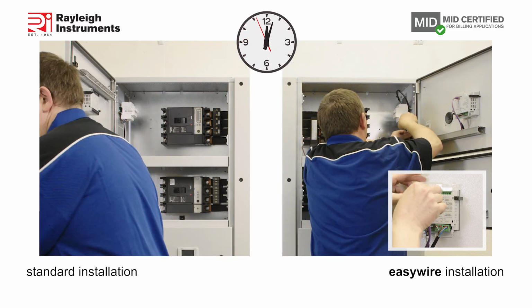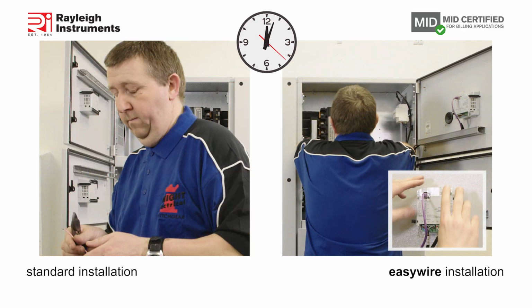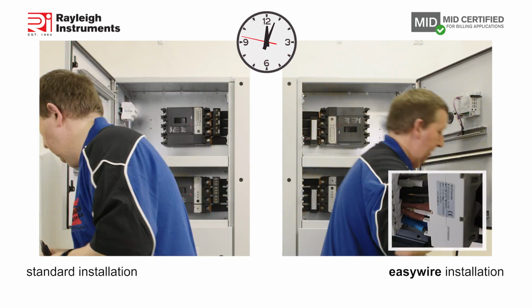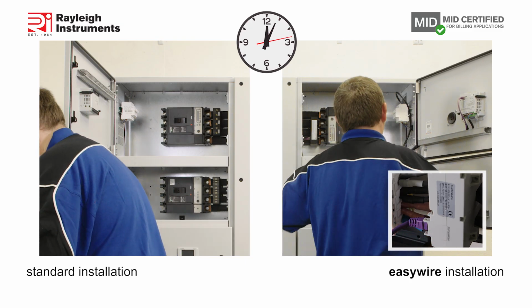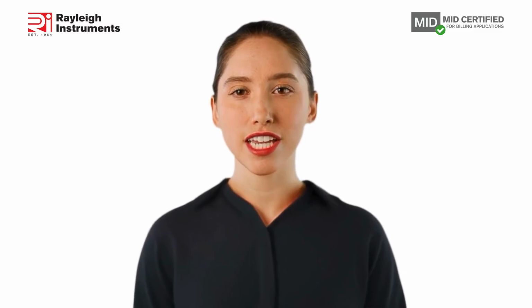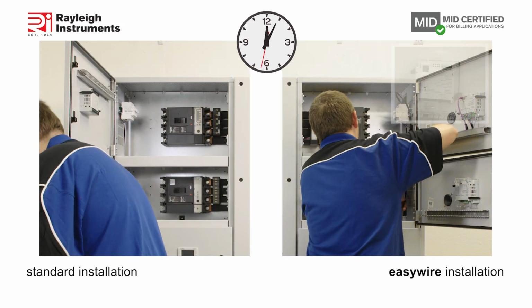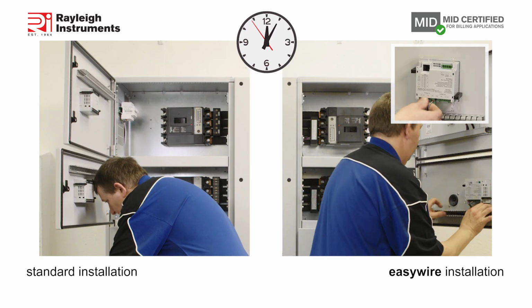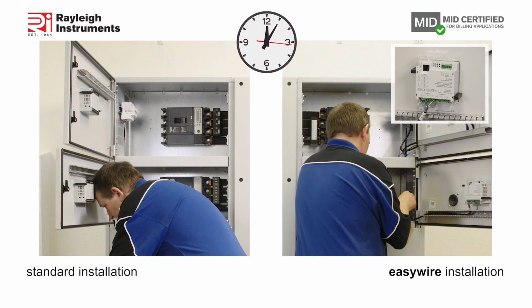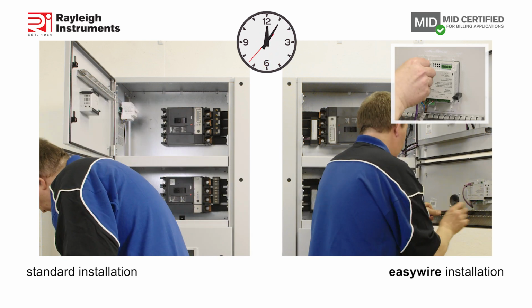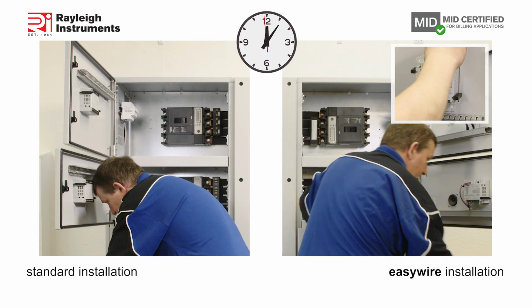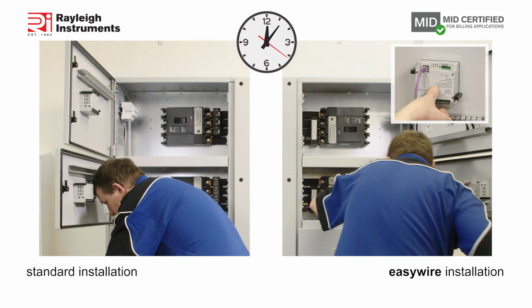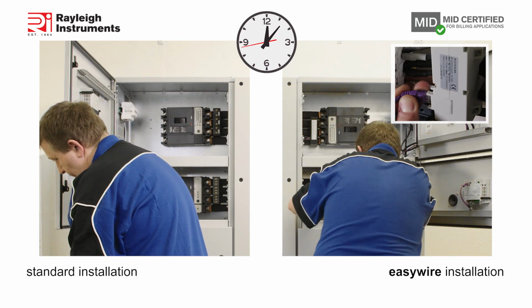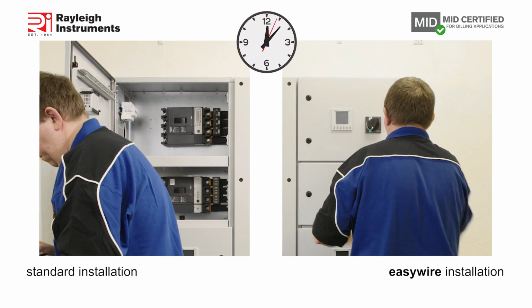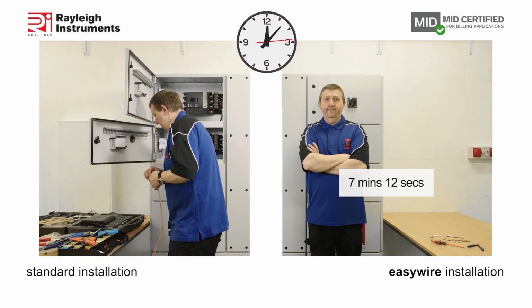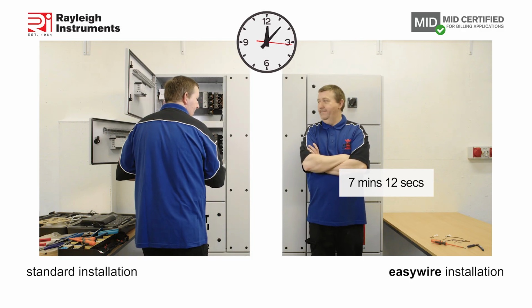Next, you will plug in the RJ45 cable into the meter, and then plug the other end of the RJ45 cable into the Easywire current transformer. That's it, done for the connection from meter 1 to CT1. Now you plug the other end of the meter-to-meter supply cable into the power-in plug of your second energy meter. That's the power sorted. Plug in the second RJ45 cable into meter 2. Then plug the other end of the cable into your second current transformer, making sure all your cables are tidy. And that's job done. Just 7 minutes and 12 seconds.